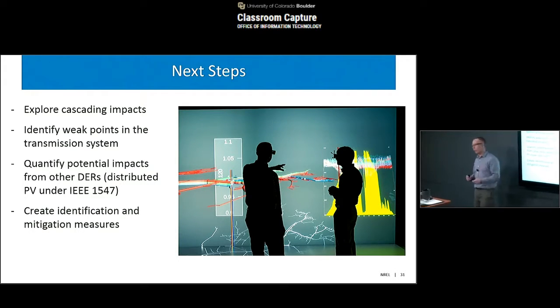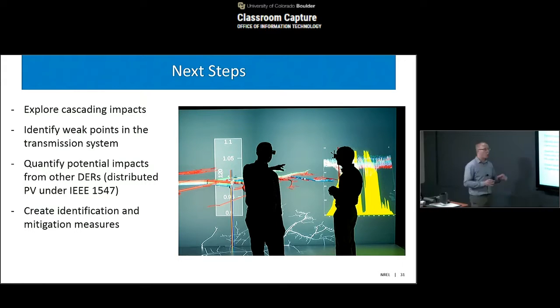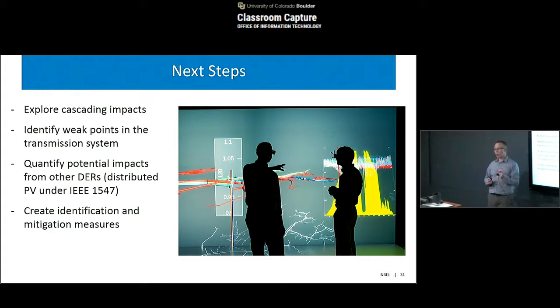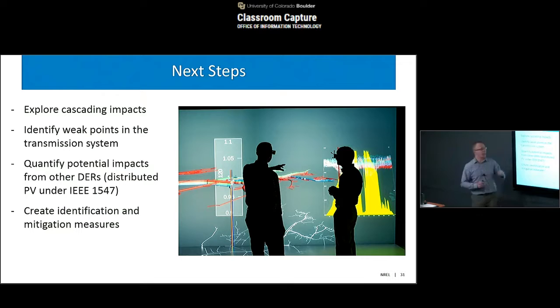Just this year we passed 1547-2018, which says now wind or distributed energy resources, in particular solar, have to be able to respond to some sorts of issues. So you have to have frequency and voltage ride through within certain bands. Now, if you go outside those bands, for example, going under 59.8, that no longer applies, and your load that you thought was there may go up even more because the distributed PV that you don't see could go off too.